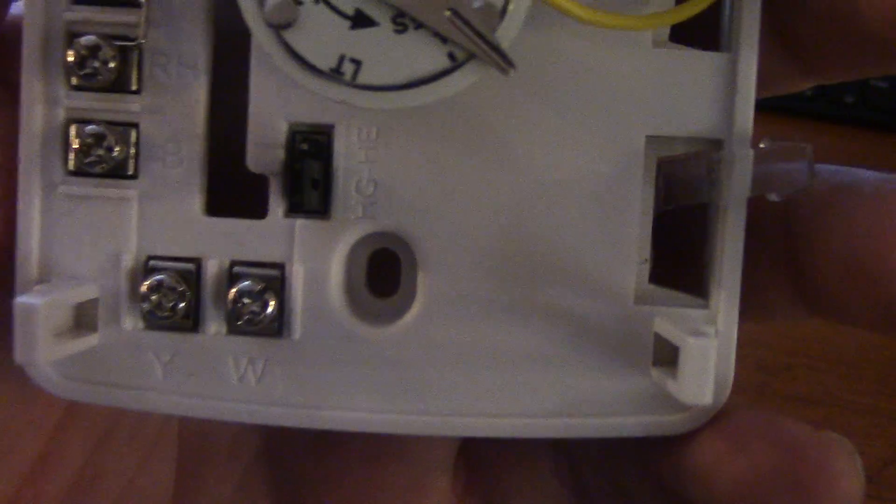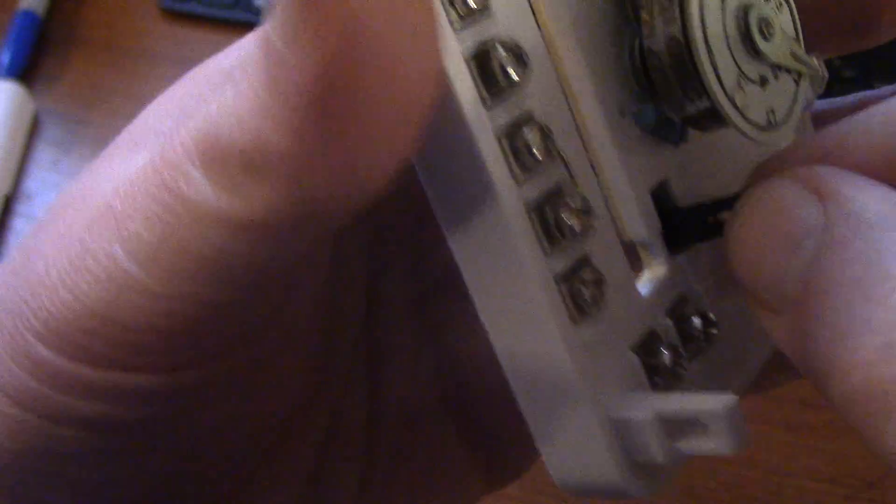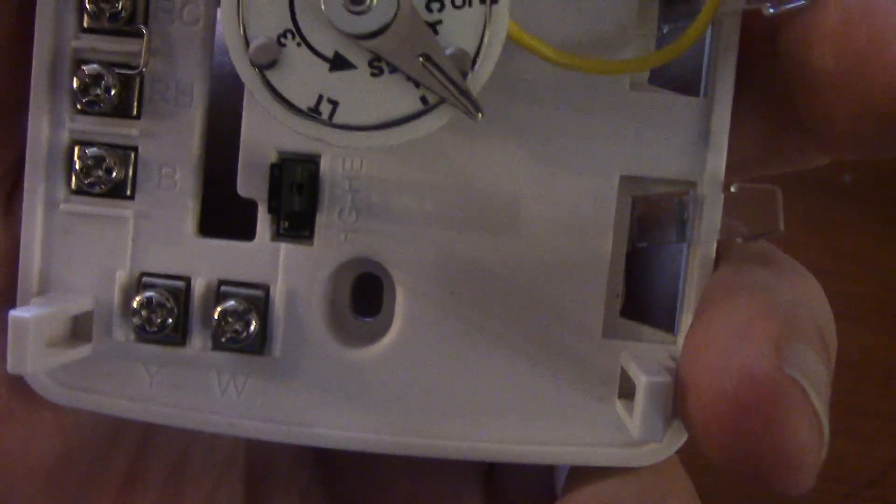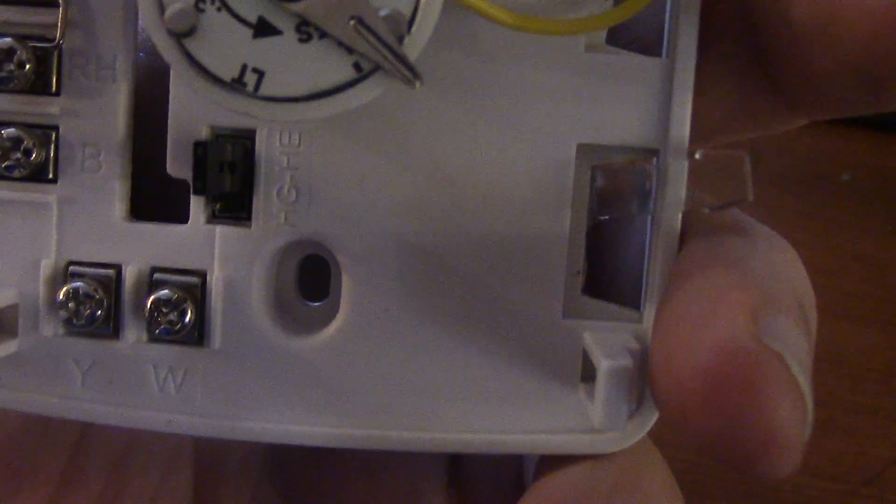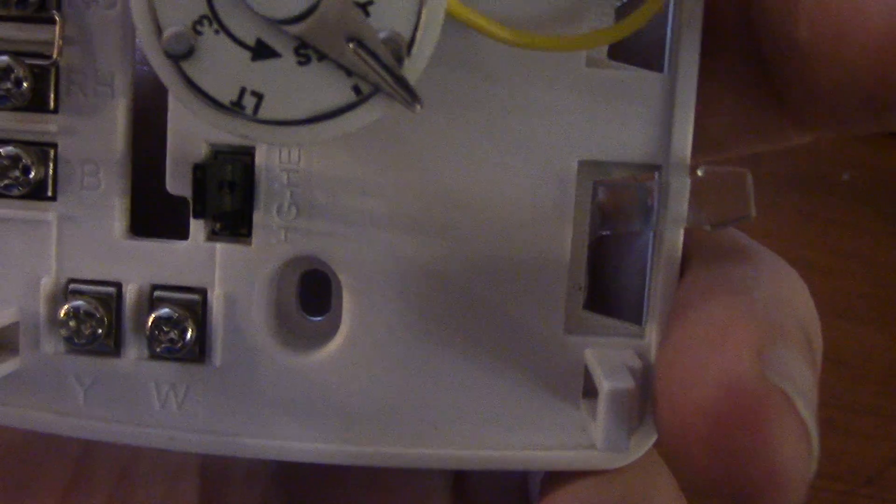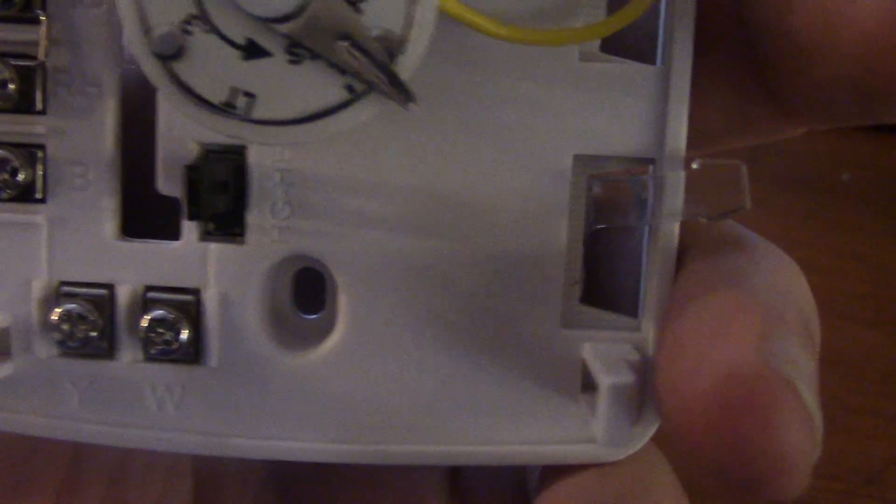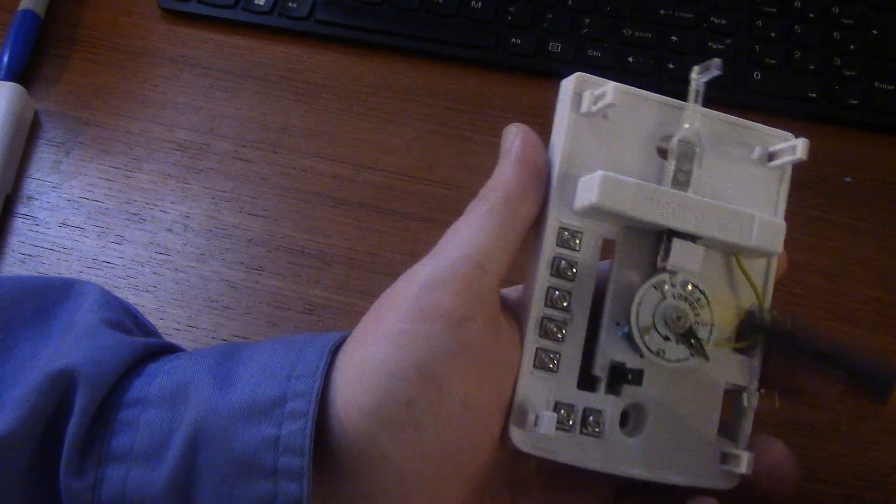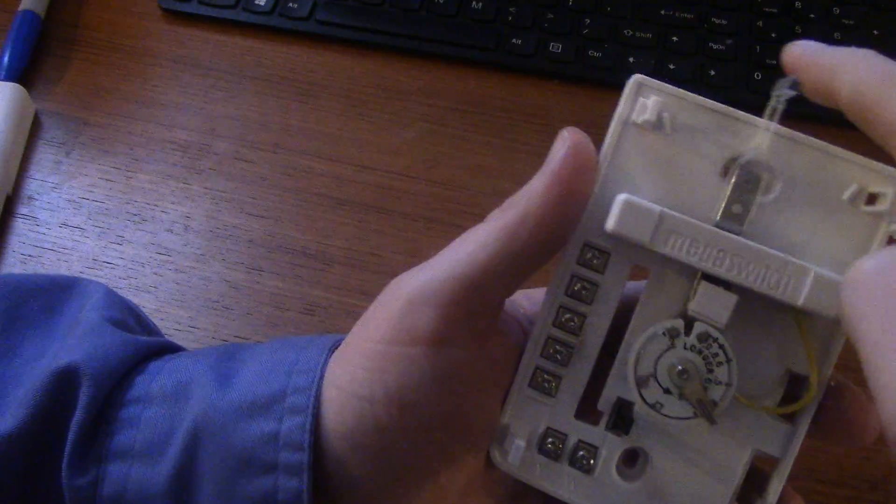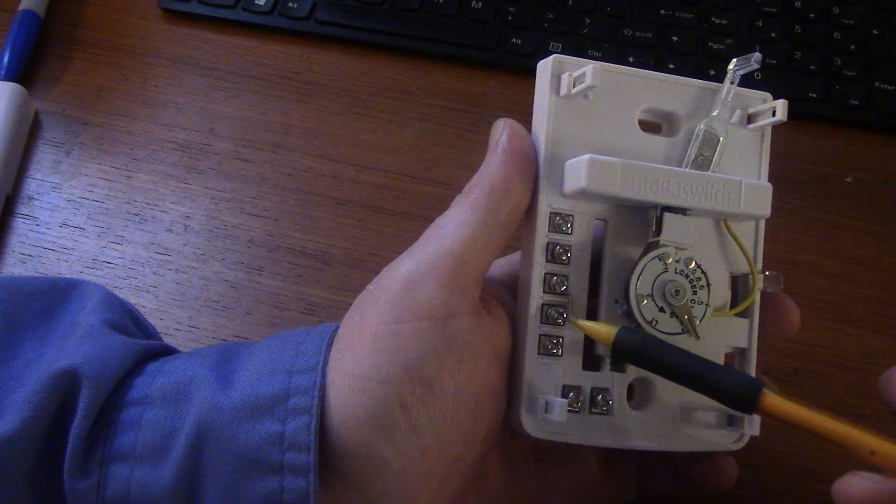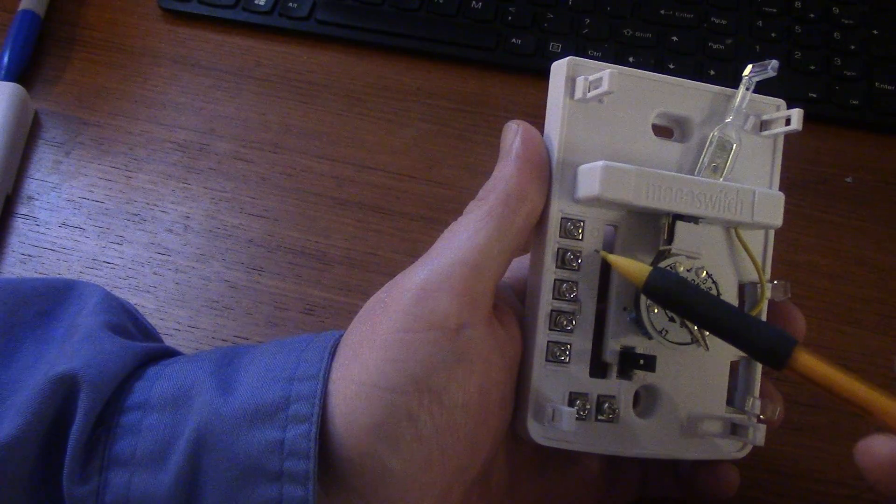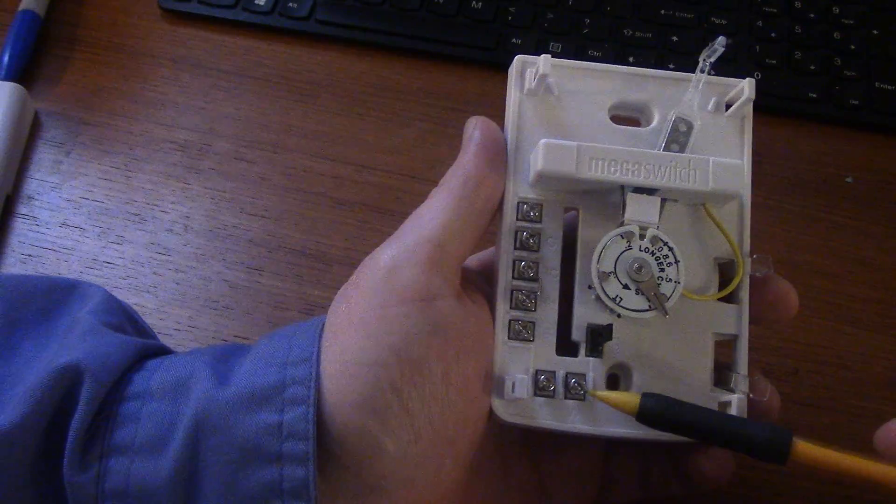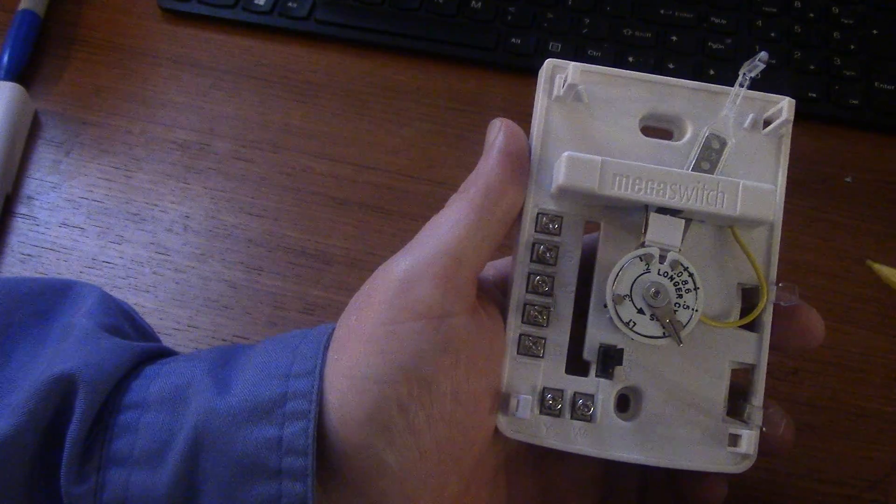If you have electric heat, you must take that jumper pin, move it over just like that to H E, which would be where you have electric heat. There is no board, no fan limit switch to turn the blower on. The thermostat itself then, once you get a call for heat, will do like that - give it a call for heat. This will then send power from R to G to turn the blower on and then power from R to W to run the heat.